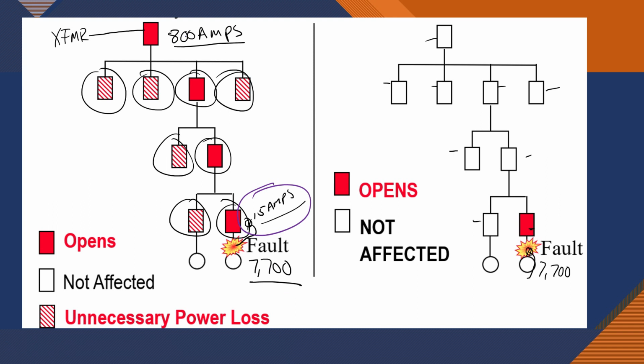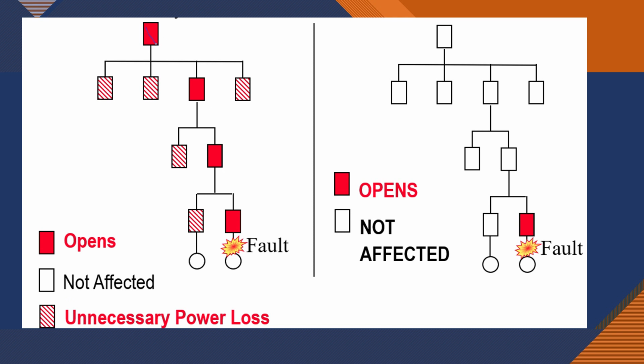But what if I've only got an 800 amp main breaker? My transformer is going to try to send 7,000, well, my transformer's not a power source, but we're not going to get into that. From the transformer to the first breaker, I could see 7,700 amps, and my 800 amp breaker could easily trip well before my 15 amp breaker. Okay, so I could trip this one off and kill the entire building.